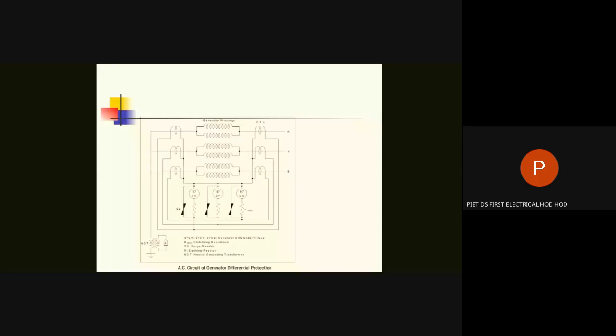You can see large generators, 210 megawatt large generators, having the double star winding, because in one winding you are passing 9000 ampere. Therefore, rather than passing 9000 ampere through a single winding, we divide the winding into two parallel parts. So through each winding only 4500 ampere passes. That reduces the problem of heat dissipation. So double star winding is shown, and the CTs for differential protection are connected as shown.